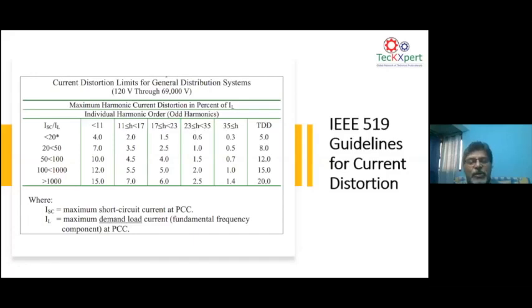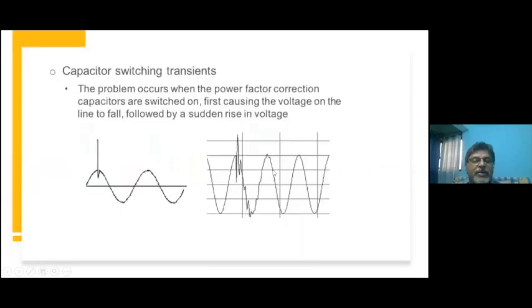And depending on the short circuit level, either it is 20 times the load current or above 1000 times the load current, you can permit your consumer to go for higher distortion in current harmonic in this case.